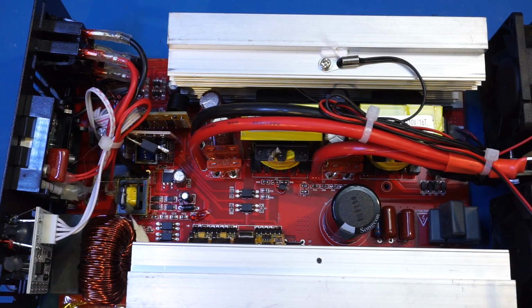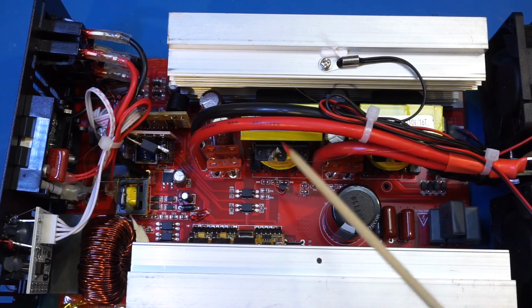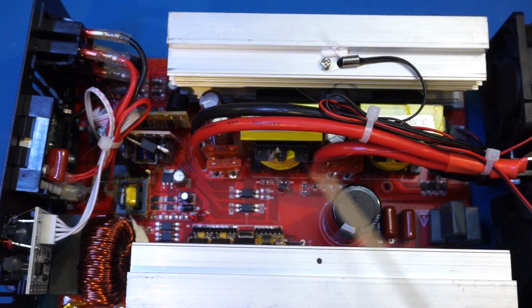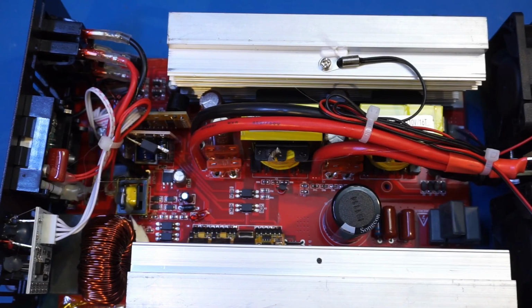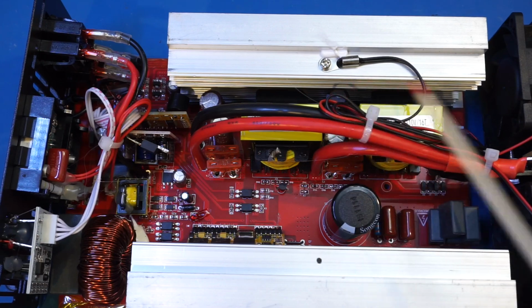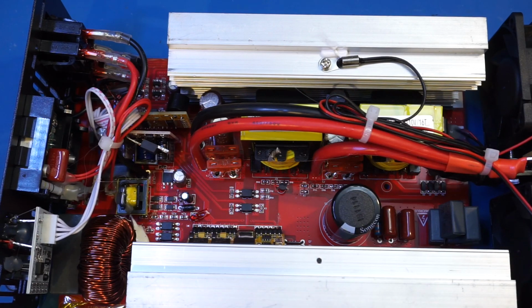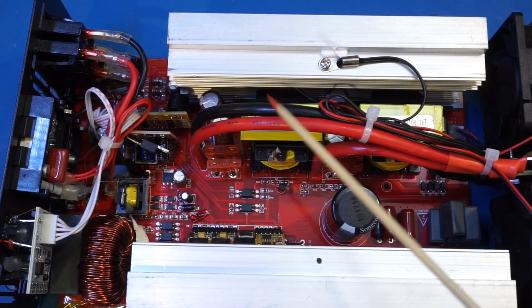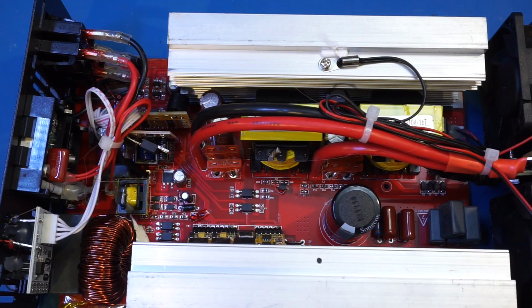Here's a better angle. You can see from the battery terminal how this wire is divided into two current paths to supply each of the inverter sections here. This kind of design, using wires to distribute the current evenly, is fairly common for higher current applications, as you wouldn't be able to push as much current through the copper on the PCB as you would with these thick wires.